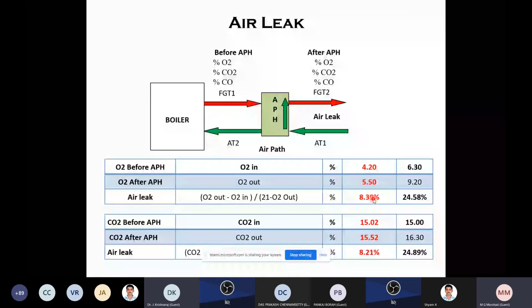The second thing is the air leak, how it takes place. Air leak is measured by seeing the O2 or CO2 before and after the preheater. How much percentage O2 is there before and how much after. This data will also be available in DCS, but for cross-checking, it is better to check at the local itself. We have to take the flue gas analyzer and take the flue gas before and after, analyze it, and see how much percent O2 and how much percent CO2 is there. In both cases, O2 before and O2 after. Then one formula is there, and then you can say this is the air leak. Normally up to 10% is allowed, 8 to 10%. If it is more than that, it is a very severe condition because your boiler efficiency will not increase, whatever you try. So you have to arrest the air preheater leak first if it is 10%.